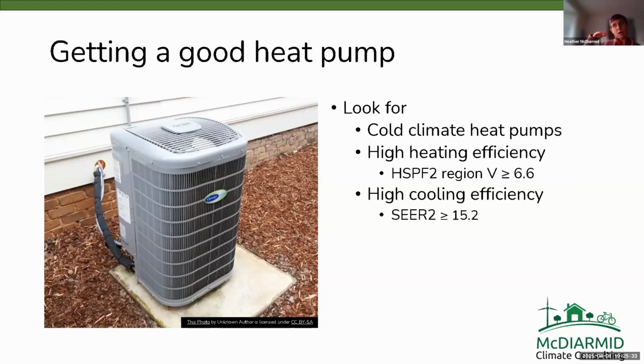That 6.6 was the minimum requirement for the Greener Homes Grant when it was running, and as far as I know it's also the minimum for the current Enbridge incentives. You also want high cooling efficiency, measured by SEER 2, the seasonal energy efficiency value, which should be greater than or equal to 15.2. Generally, if you're over 6.6 on HSPF2, you'll be over 15.2 on SEER.